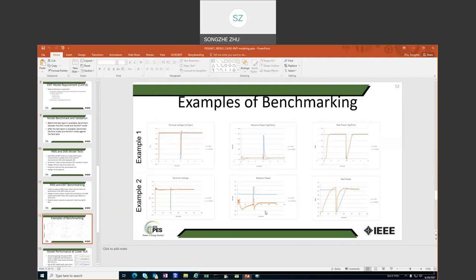We got an explanation from the OEM that it is because the actual ramp rate for the inverters is a variable ramp rate. It's not always just one ramp rate under all conditions. But in the generic model, we can only model one ramp rate.